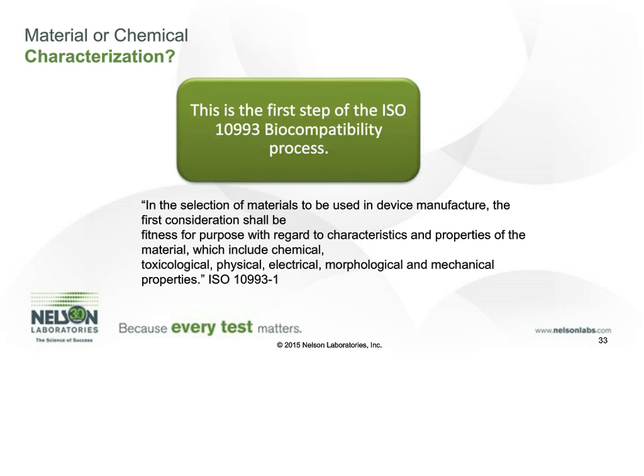overall evaluation of material. Sometimes when we do a material evaluation and we look at how the device is used, if it's on skin, for example, or very limited or low risk use, then a chemical characterization may not be needed. We might be able to evaluate risks for the patient just based off of the material evaluation. In other aspects, the material evaluation may tell us that we need a chemical evaluation to address some of those risks. And then depending on the chemistry, we may need to address other risks by actually doing biocompatibility testing.